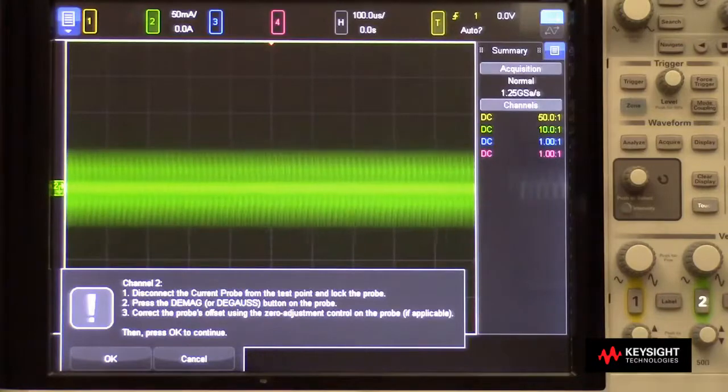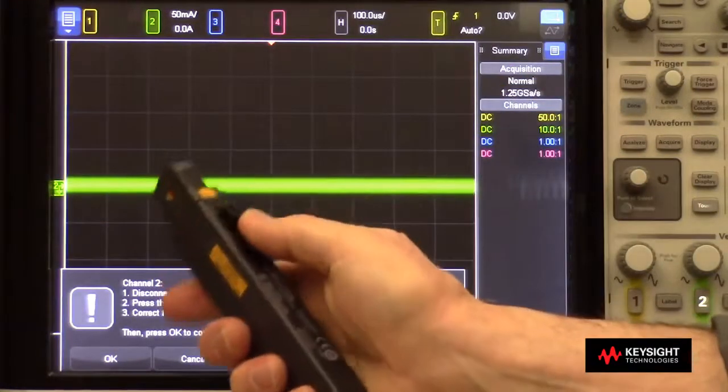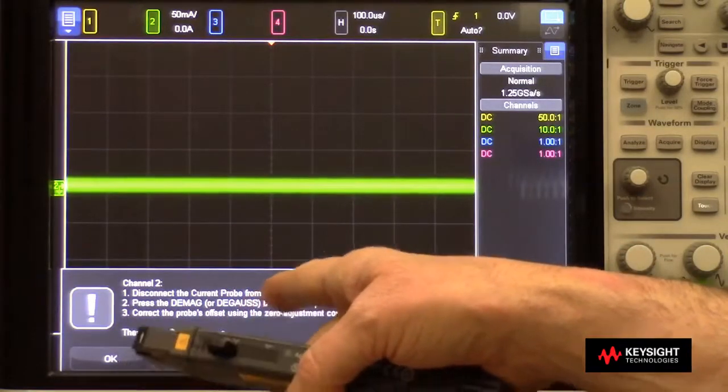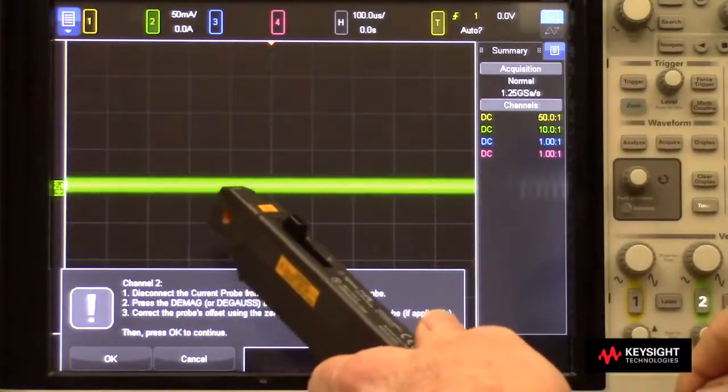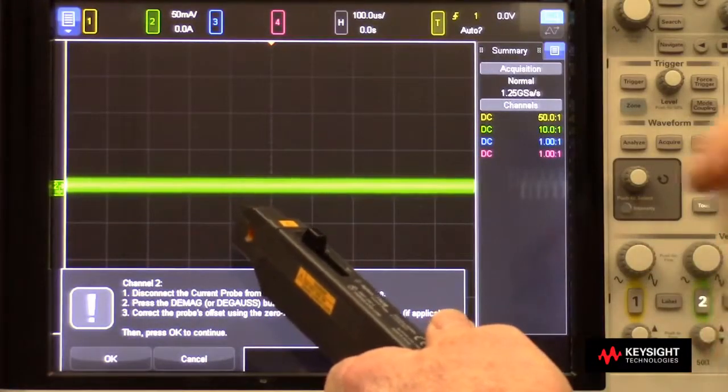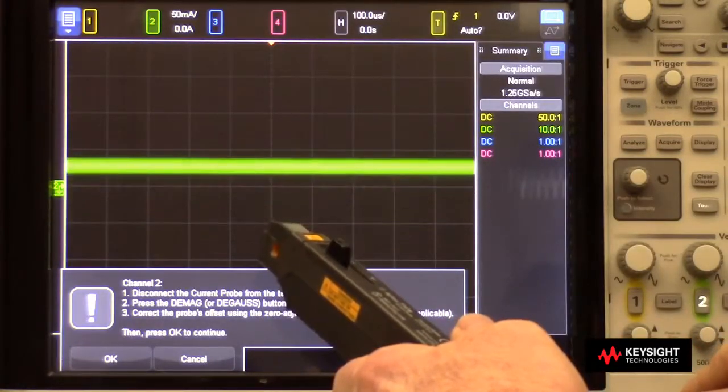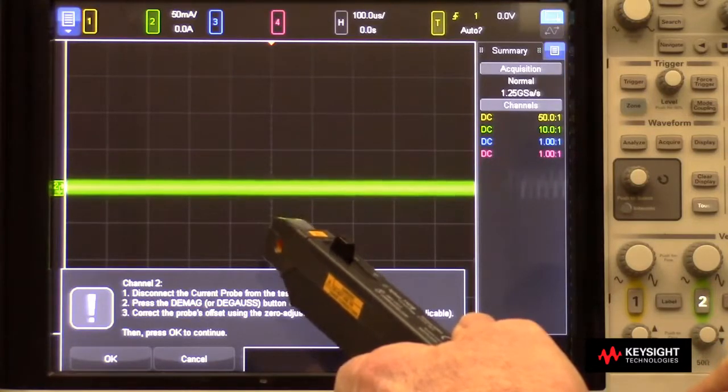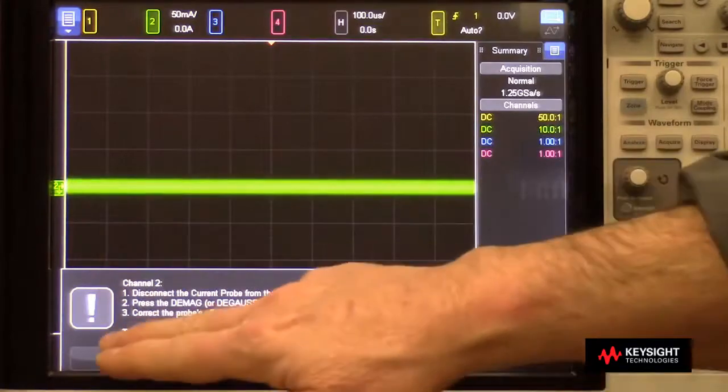Next, it tells me to disconnect my current probe, which you can see here, lock it, and then it says to press the DEMAG button or sometimes called a degauss button on the probe. I'll do that because the probes can build up a field on them. And then I can also manually adjust the offset. So I'll get it as close to the ground indicator as possible, but it still may not be precise. I'll press OK.